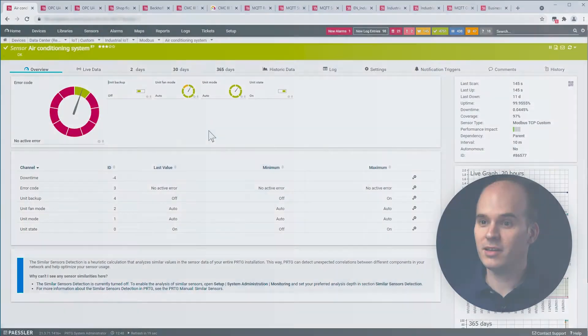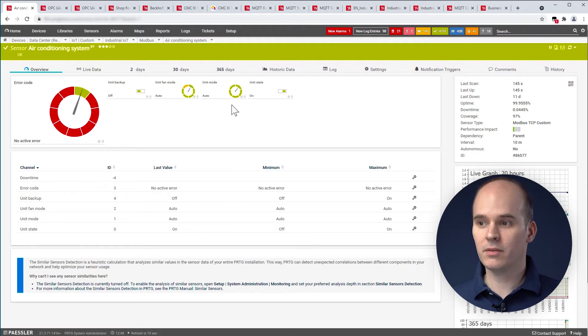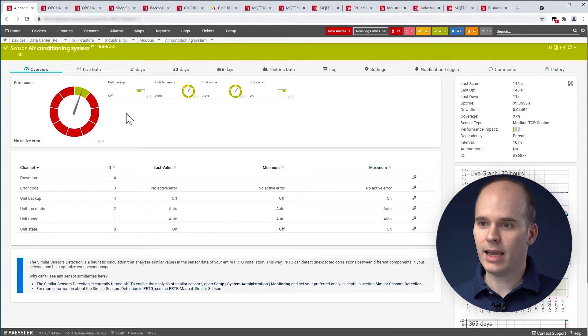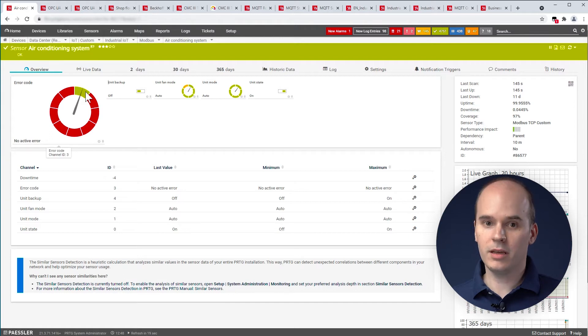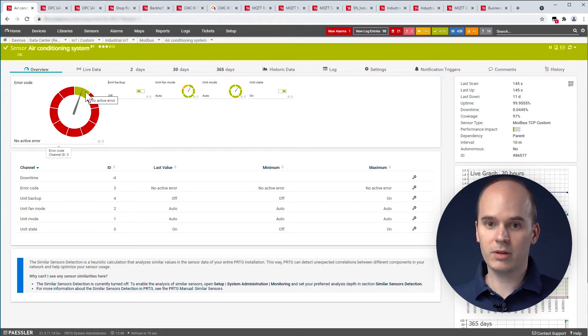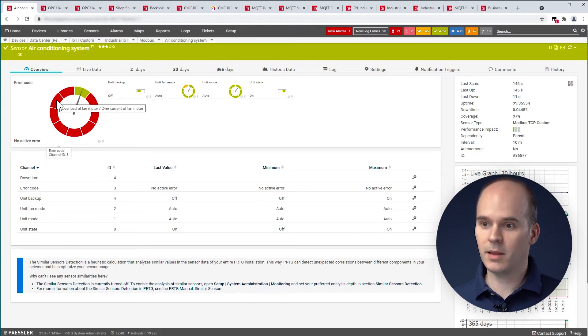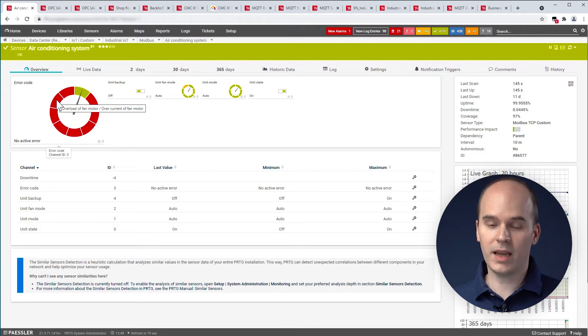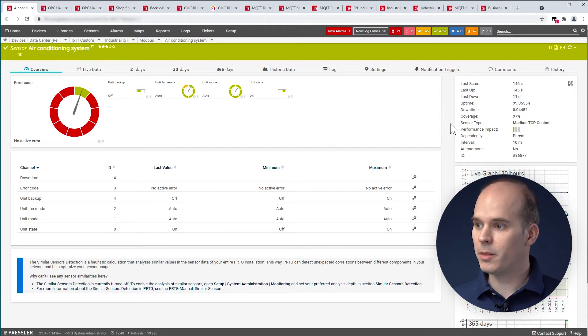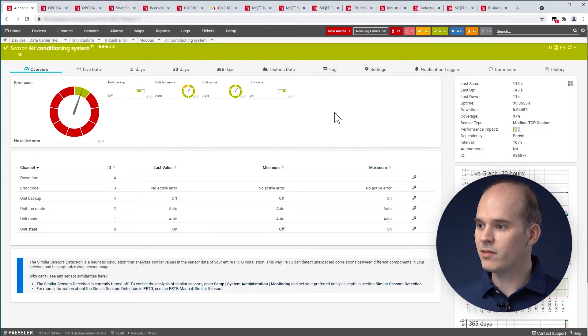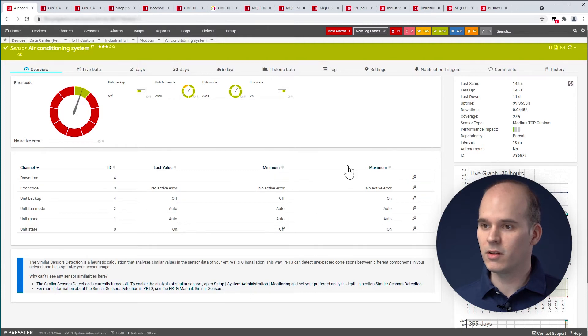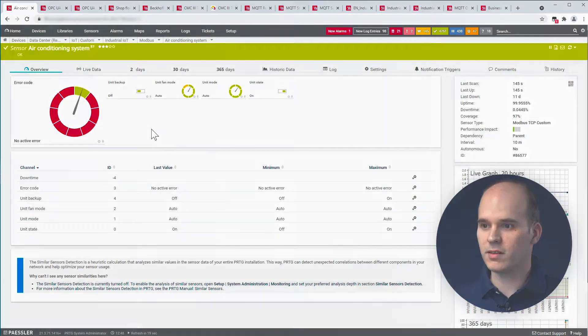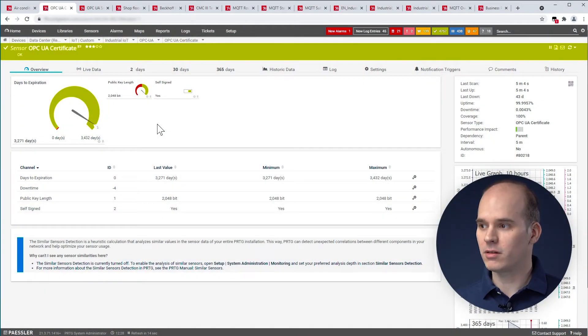What we see here is the sensor of an air conditioning system. We see different information. These are called channels in PRTG. The overall status is displayed here and indicated by green. Also, the gauges pointer is here on green, so no active error is there. Another possibility is that there is an overload of a fan motor, so that there is a certain type of error. On the right hand side we see the sensor type. It's our Modbus TCP custom sensor, what you can find in PRTG. In the lower area you can see the last values, the minimum values and also the maximum values of this sensor.